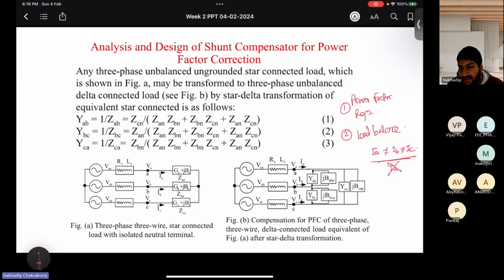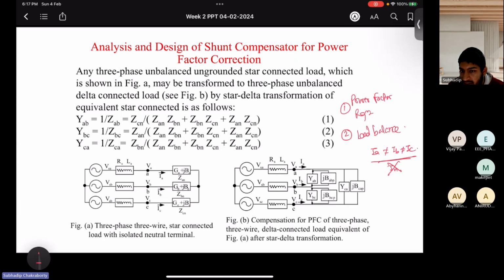Can zero sequence currents exist in three-phase, three-wire systems? No. Why? Because how does the zero sequence current look? Zero sequence current of phase A, phase B, and phase C all have zero phase displacement between them, whatever the magnitude. Their amplitudes are the same and their phase shifts are zero. So these three-phase, three-wire systems cannot contain zero sequence currents or neutral currents. Please note it: zero sequence currents and neutral currents are absent in this kind of systems.